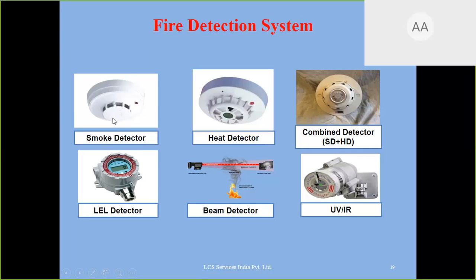Smoke detector. Second is heat detector. This senses heat, a temperature rise, and then it will give you an alarm. Third is the combined detector, which is SD plus HD. This detector will sense smoke as well as heat. Nowadays, people are not installing separate smoke or heat detectors. They are installing the combined detector, which is known as SD plus HD. Correct? I don't want two detectors, smoke separately and heat separately. So when we have a combined detector, it will sense smoke or heat, whichever is there.